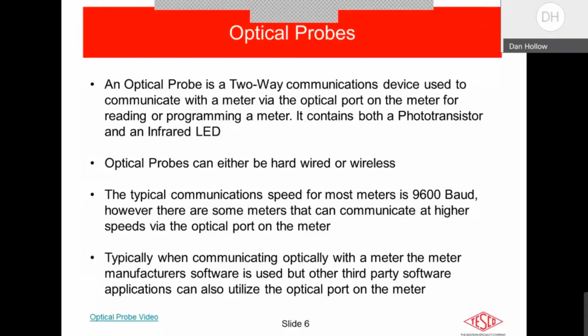So that was very convenient for utilities that did not want to run 3-4 different pieces of meter manufacturer software to extract the data and save it as an HHF file on that local laptop. That HHF file would then be imported into another system, such as MV90 or other head-end systems that could import it. HHF is an industry standard format now and has been for quite a few years for devices read in the field optically rather than remotely through various communication mechanisms, whether hardwired phone lines, direct IP, or cellular communications. So there are lots of other ways to get the data in.